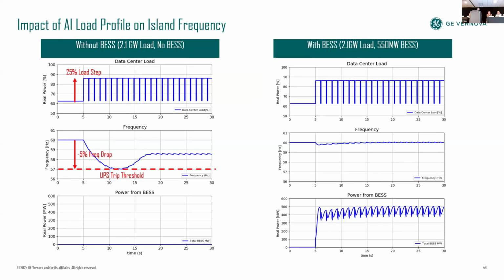So when we have a system with only gas turbine units, for example, the 25% load step, which is modest given the type of profile that we have seen, causes the frequency to dip below 5%, right? And this 5% is typically the threshold where the UPS starts to pick up the load. Which means if you don't have any other mechanism to compensate, this profile will cause the load to be lost from the plant point of view, right? And this 5% is also typically the point where other equipment starts tripping, the plant auxiliaries, even the protection in the gas turbine itself, right?